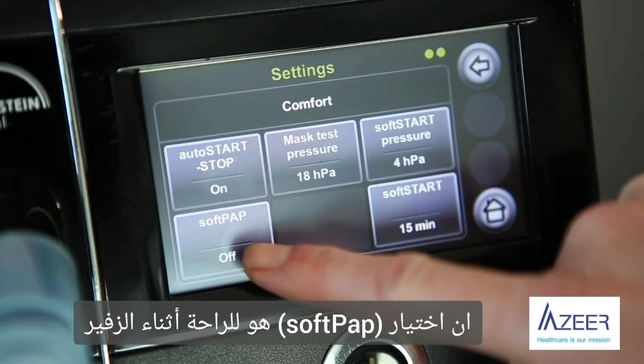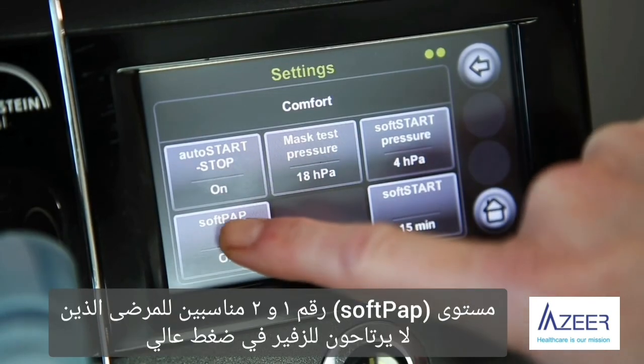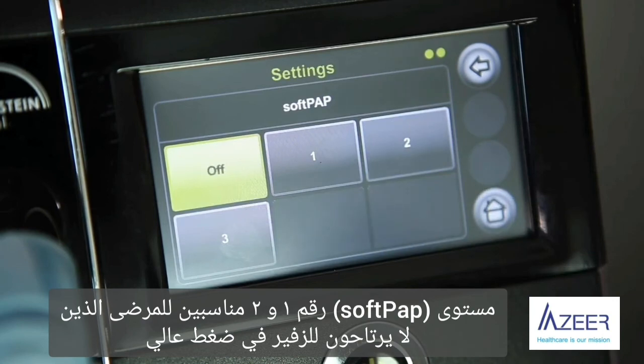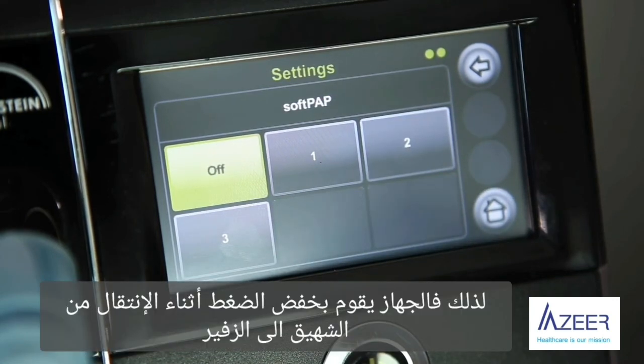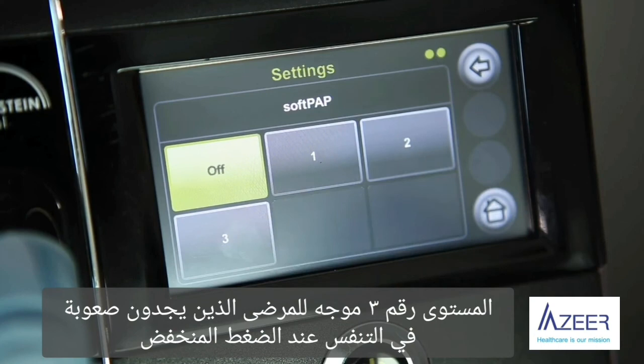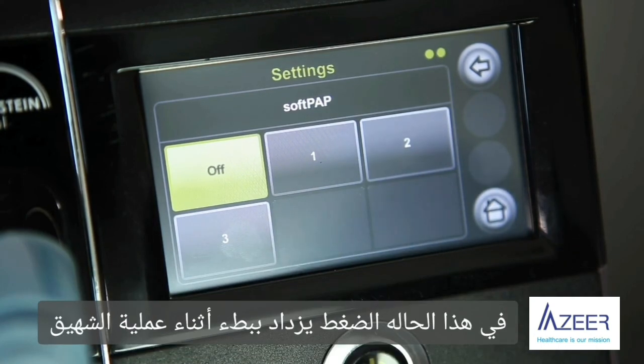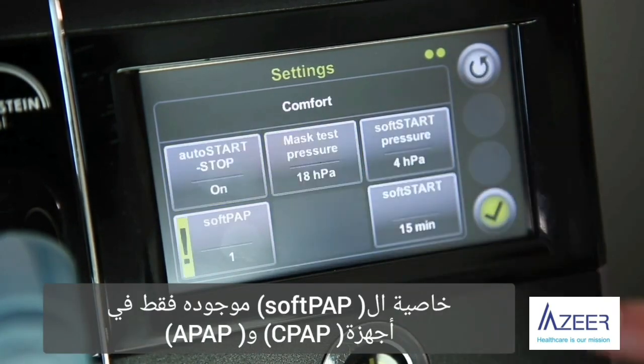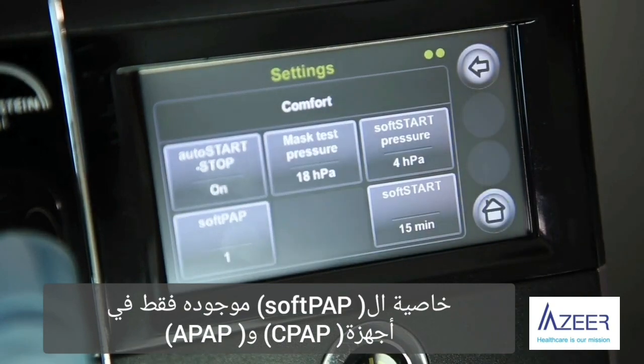softPAP is the exhalation relief. softPAP levels 1 and 2 are intended for patients who find it unpleasant to exhale against high pressure. softPAP reduces the pressure during the transition from inhalation to exhalation. Level 3 is intended for patients who feel respiratory distress at low pressure; in this case, the pressure is increased slightly during inhalation. softPAP is only available in modes CPAP and APAP.